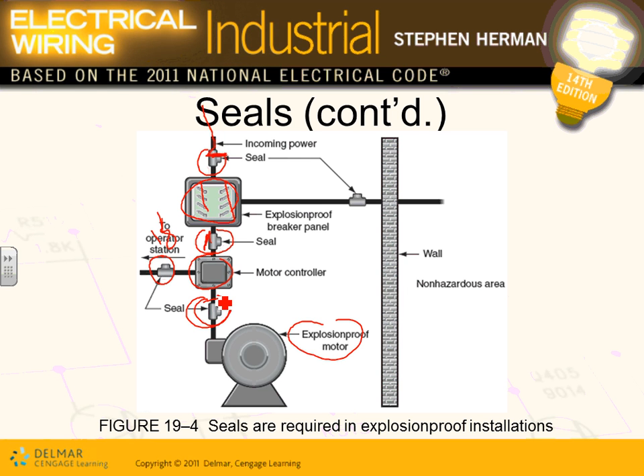So everything that can create an arc, guys, like a circuit breaker, a switch, a magnetic contactor, anything that interrupts the power, a generator, a motor, a transformer, they have to be explosion-proof and they have to be sealed around it. Any comments, guys? Any questions about sealing? You have to also seal every time you exit to a non-hazardous location. Within, I believe, 10 feet of that non-hazardous location, you have to seal. So you don't allow the gas to seep into different areas here. And, right? You're in a gas area, guys, gas and vapor, or dust. So you need to seal.